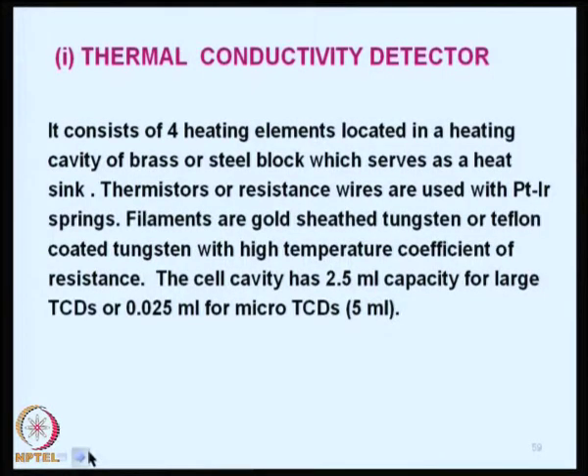We are going to discuss the thermal conductivity detector. It consists of 4 heating elements located in a heating cavity of a brass, glass, or steel block which serves as a heat sink. Thermistors or resistance wires are used with platinum-iridium springs, and filaments are gold-sheathed tungsten or Teflon-coated tungsten with a high temperature coefficient of resistance.